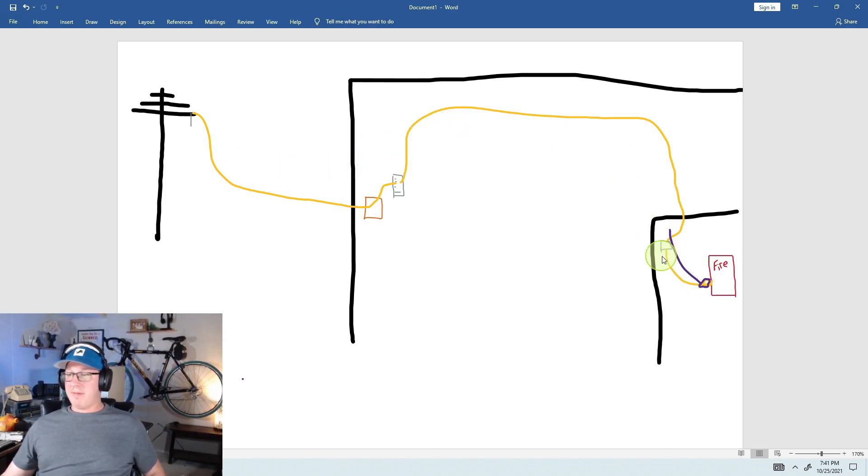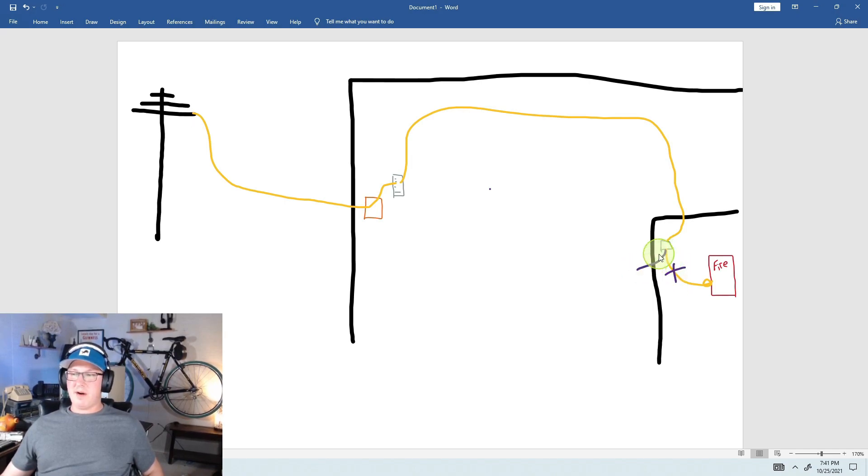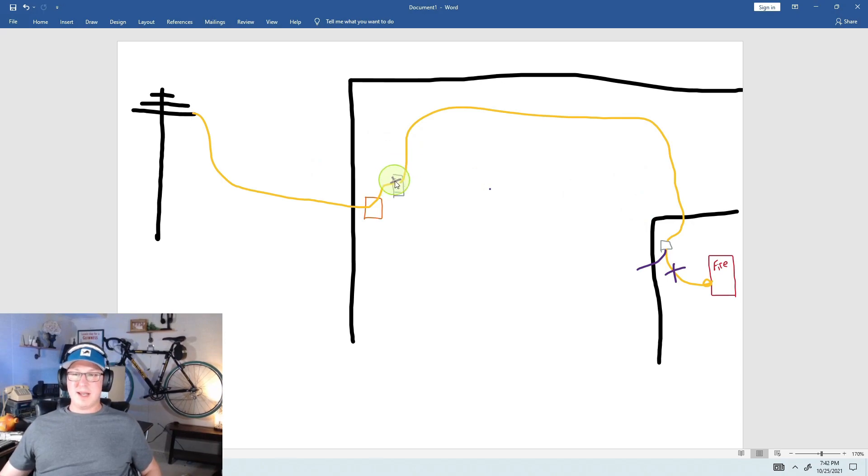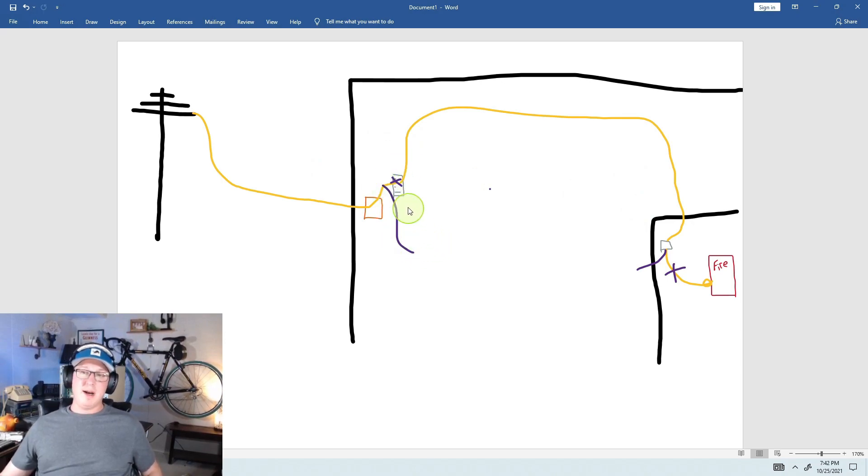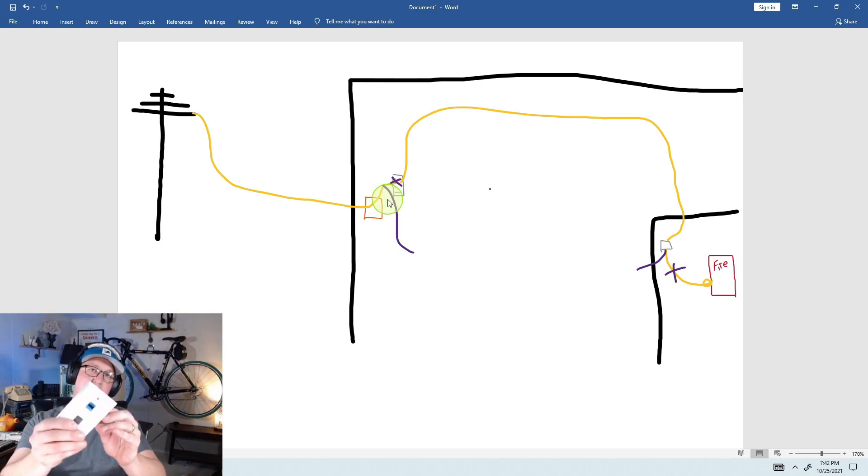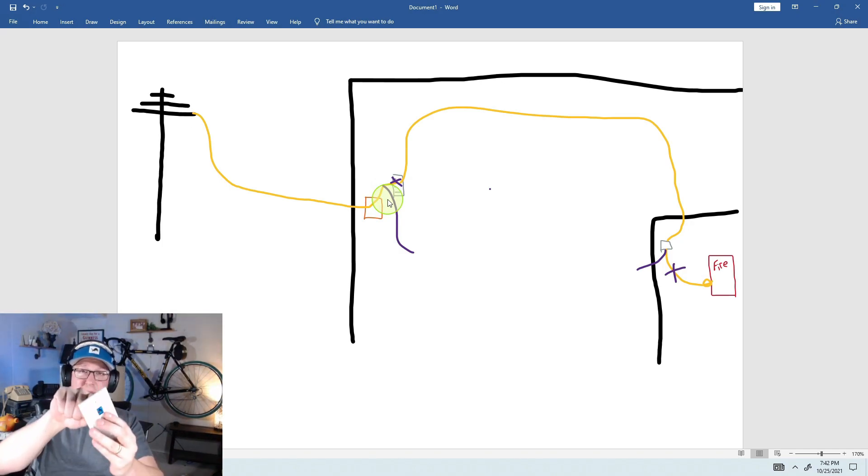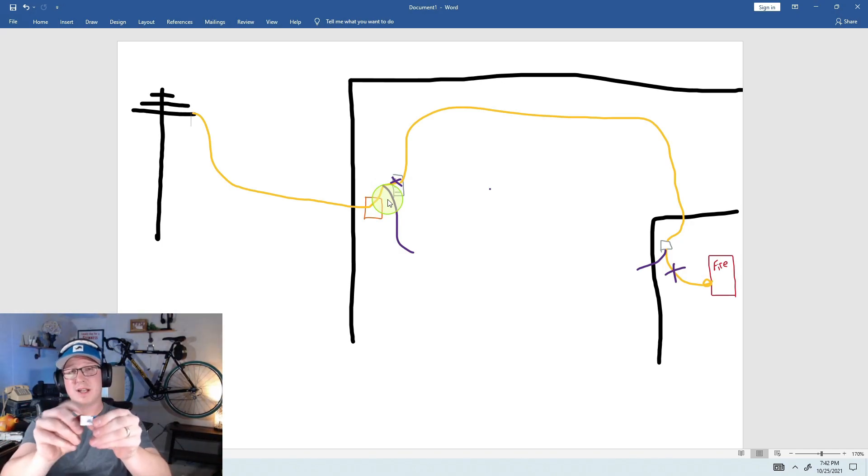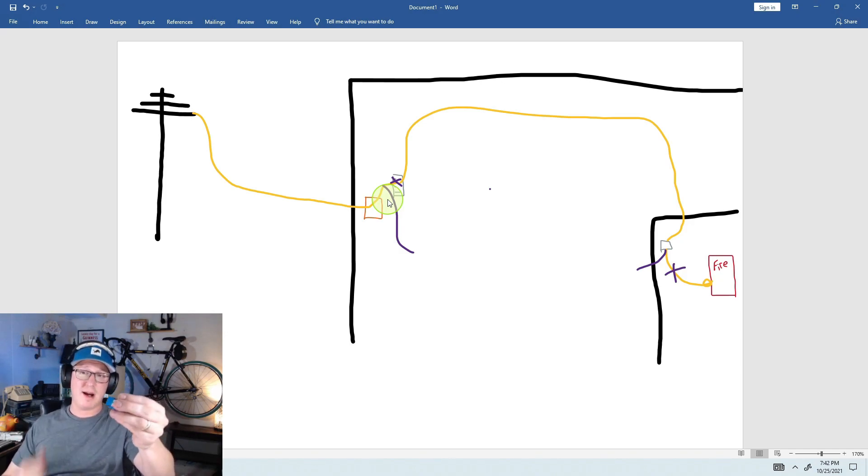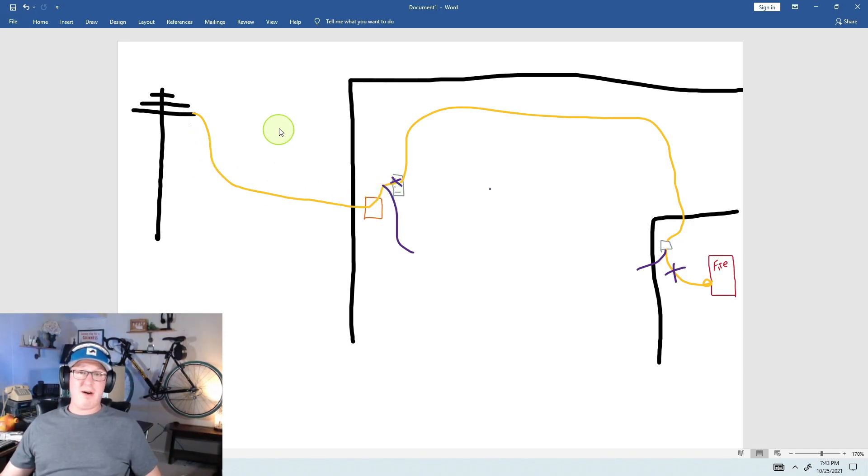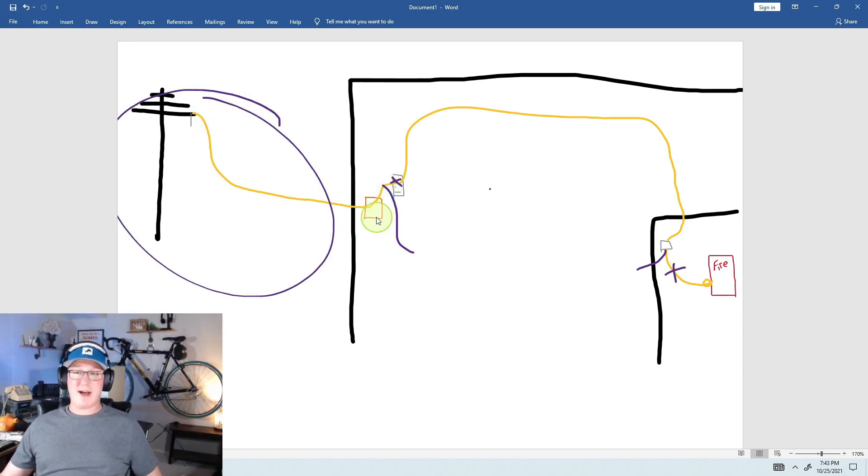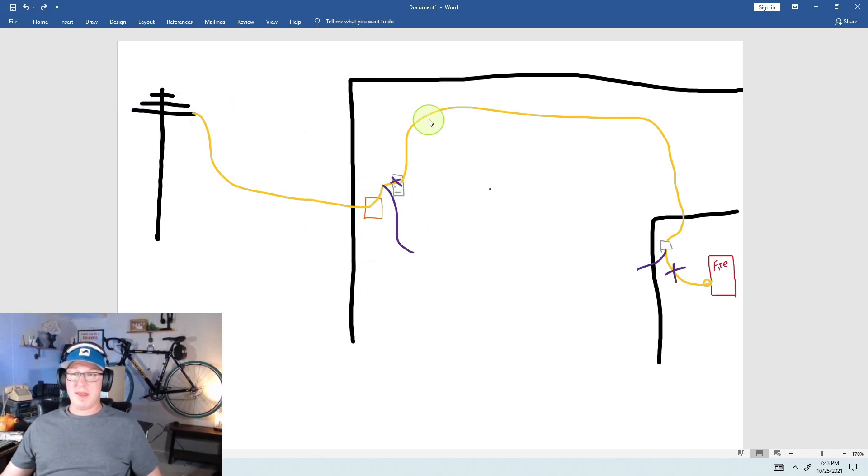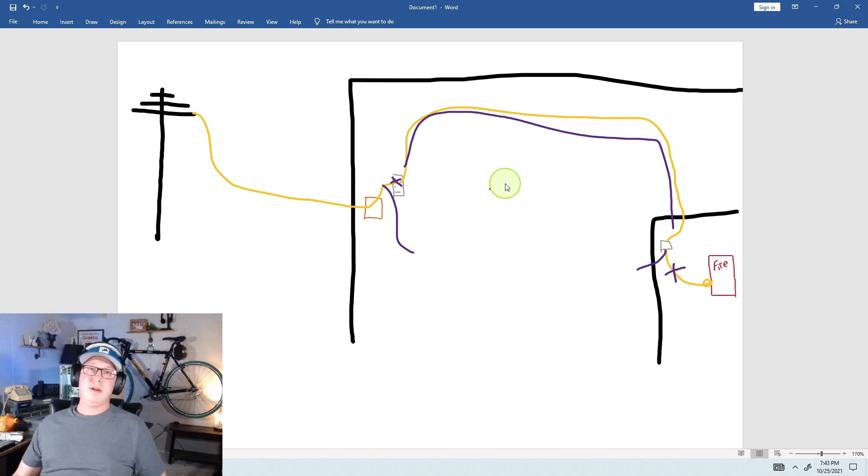I would test from here back. As long as I can call in and out from here back, I know that it's something wrong with the fire panel. I'll disconnect this line from my biscuit, and I'll hook my phone directly up to the biscuit, call through. If I still can't get out, I'll do the same thing over here. I'll disconnect from here, and I'll plug my butt set in right here. Because this is connected to a wafer, you'll have to pull this wire, and then you'll connect it down to one of these mods. At this point, if I still can't get out, I know that it's on my provider side because it's past my DMARC. But if I can get out from here, then I know that it's somewhere in this wire, so then I have to troubleshoot this wire.